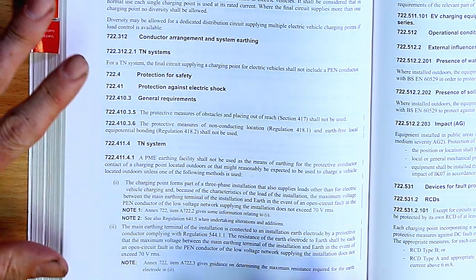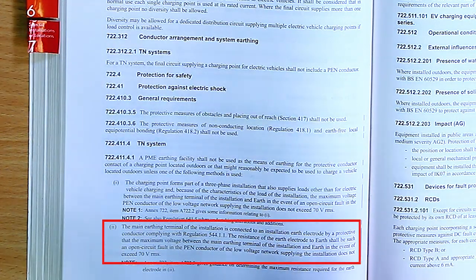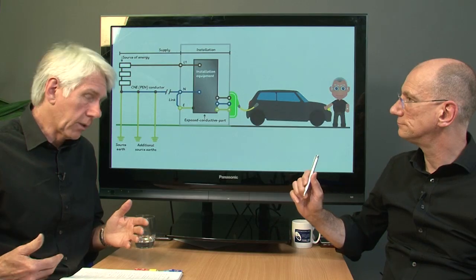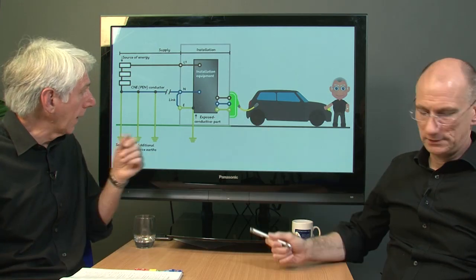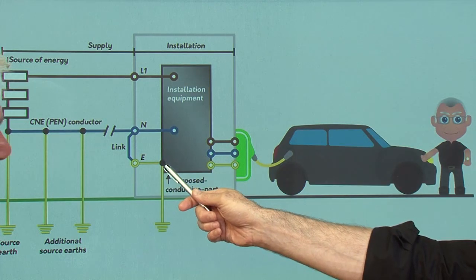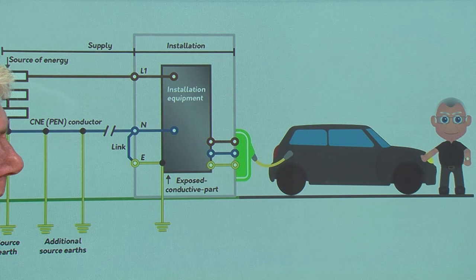Number two: the main earthing terminal of the installation is connected to an installation earth electrode by a protective conductor, and it goes on to detail how. Let me flick between the two - it's shown here for convenience: this is the main earthing terminal, and this is the supplementary earth electrode.